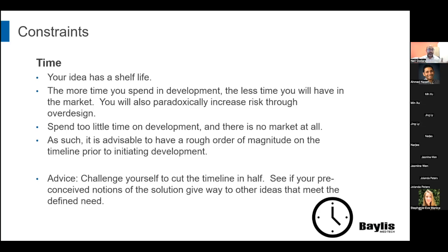And that'll be a theme you'll hear me talk about a lot today, is reducing the scope and risk of your work, because medical devices are very complex and very burdensome to get out, and they only get more risky the further out they are from the time you start designing it. Once they're in the field, all the variables of how physicians use it or the patient's disease presentation, you don't control that. So therefore, having less complexity up front gives you the best chance of fully validating, verifying, and assuring stability of your product or your design, so that it has the best chance of accommodating all the unknowns in the open market.